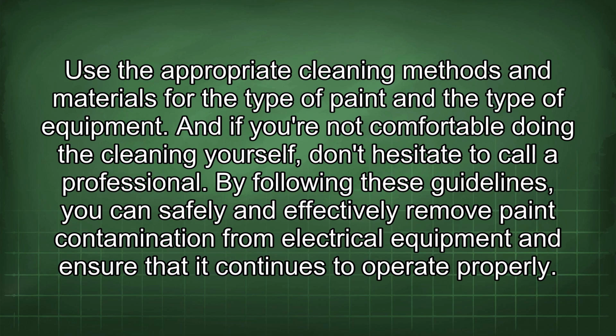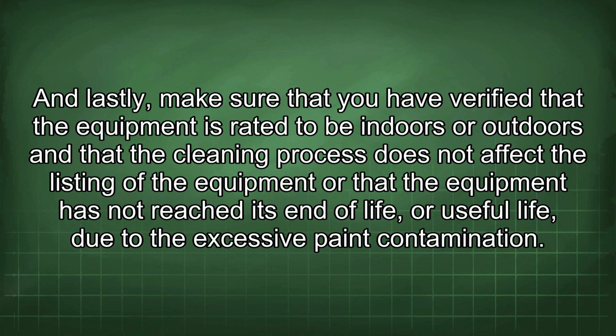By following these guidelines, you can safely and effectively remove paint contamination from electrical equipment and ensure that it continues to operate properly. And lastly, make sure that you have verified that the equipment is rated to be indoors or outdoors, and that the cleaning process does not affect the listing of the equipment or that the equipment has not reached its end of life or useful life due to the excessive paint contamination.